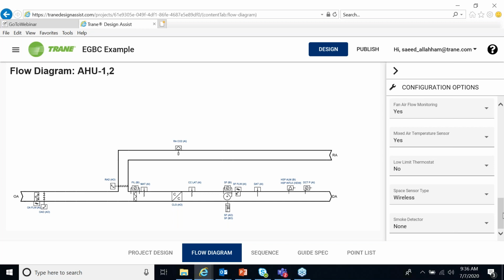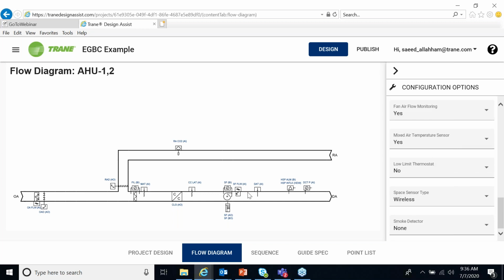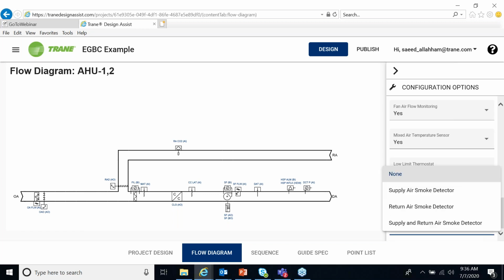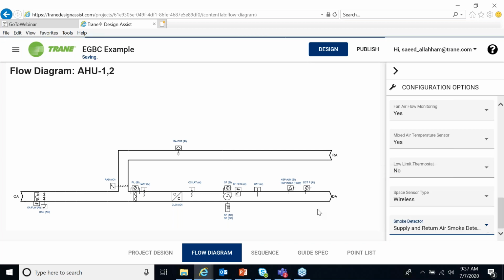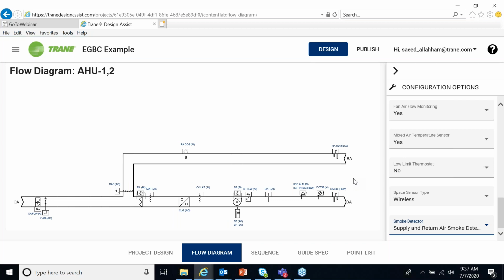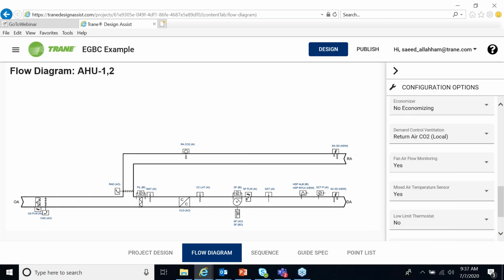Now, as we mentioned, whatever changes we make here will be reflected immediately here. For example, smoke detector, I put no. I can put smoke detector on the supply, on the return, or supply and return. Let's put both of them. So as you see here, it added smoke detector on the return and on the supply. So whatever changes we make here, it will be reflected.